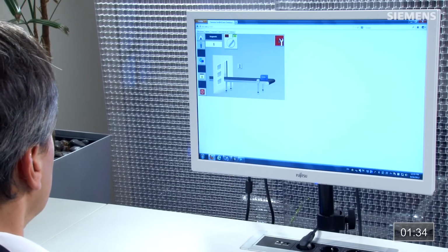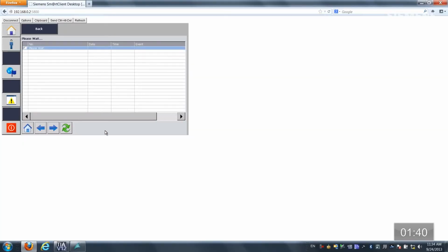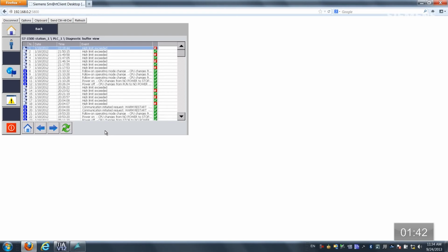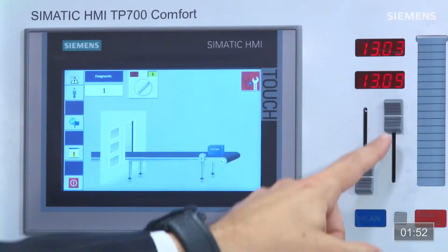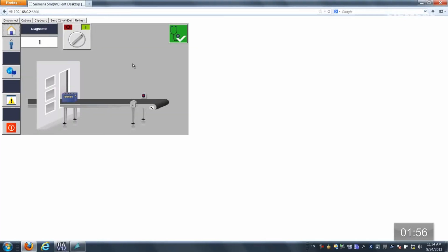Now I can click on it, go straight to the ActiveX control for diagnostic viewer window, click on this button, and then it's going to go back and find us exactly where this diagnostic is. It's a high limit exceeded, that is correct. And I could even drive all the way down to the actual point level in this architecture of hardware to find where this fault is. If I solve my problem and click on back, I'll see that everything's fine.